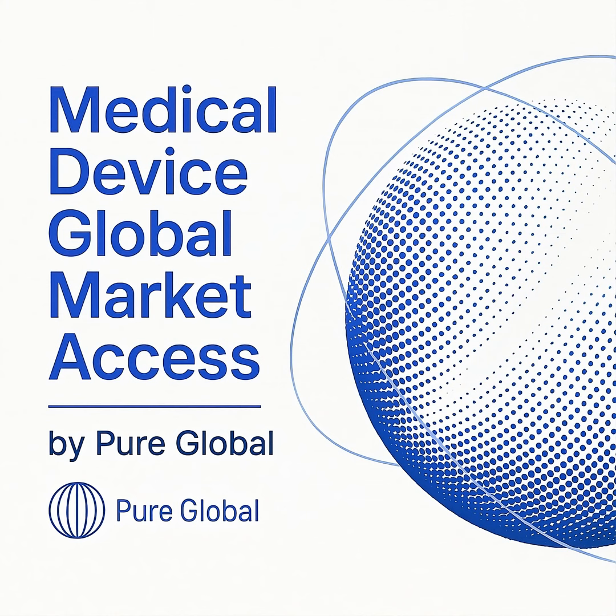In this episode, we will explore the critical requirements for clinical evaluation and clinical investigations for medical devices, focusing on the framework established by the European Union's Medical Device Regulation, or MDR. Under the EU MDR, which is Regulation EU 2017/745 and has been fully applicable since May 26, 2021.